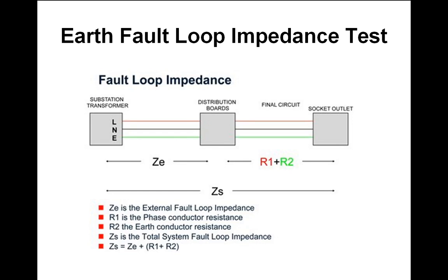You're dealing with 50 hertz, and with the impedance, you look at reactances which are in the system. There's capacitive reactance, which is going to be very low for 50 hertz. But if you've got some wire coiled up, you will also have an inductive reactance. A reactance means that the apparent resistance of the component, the wire, or whatever you're dealing with, is changing with frequency. So the DC resistance tells you this is 10 milliohms, but then you put an AC current through it, and you find that the resistance is actually more like 50 milliohms, because you've got some curled up stuff somewhere, and you get some inductance, possibly some capacitance as well, and that changes the value.